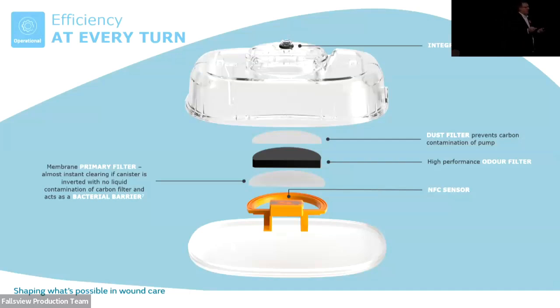So what we've done is we've repurposed the tamper detection bit to allow us to sense the fluid level in the canister. And when the fluid short circuits across the tamper tag, the canister sensor transmits to the device and alerts the user that the canister is nearly full. So it's a direct measurement for canister full sensing, which we're very happy with.